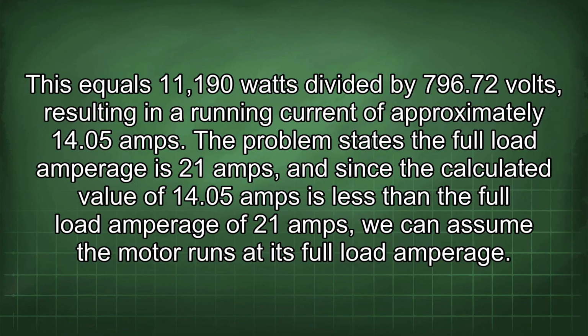The problem states the full load amperage is 21 amps, and since the calculated value of 14.05 amps is less than the full load amperage of 21 amps, we can assume the motor runs at its full load amperage.